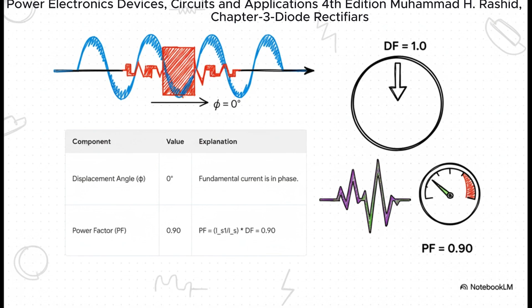Let's break this table down, because this is where it all comes together. First, check this out: our displacement factor is a perfect 1.0. Why? Because the fundamental part of our current is perfectly in phase with the voltage, so no timing problem. But when we calculate the true power factor, which includes the distortion, we find it's only 0.90. That distortion has literally cost us 10% of our potential power efficiency.